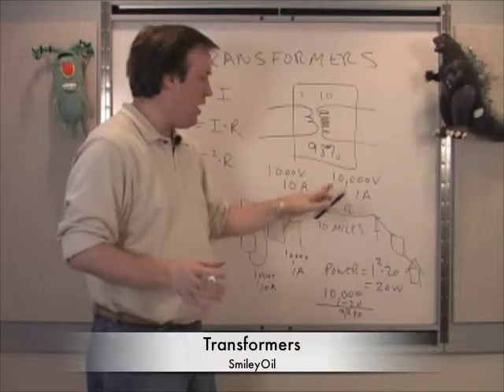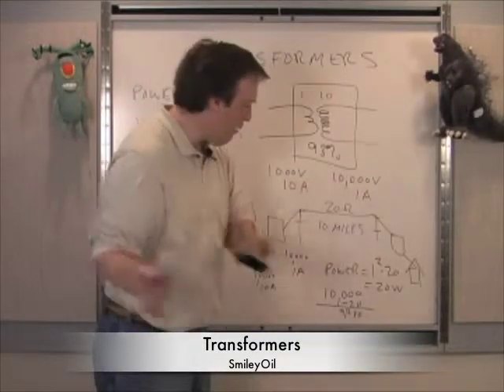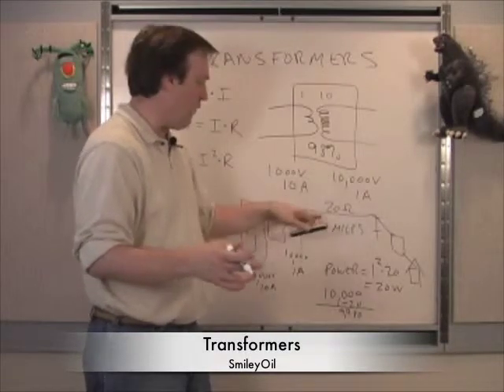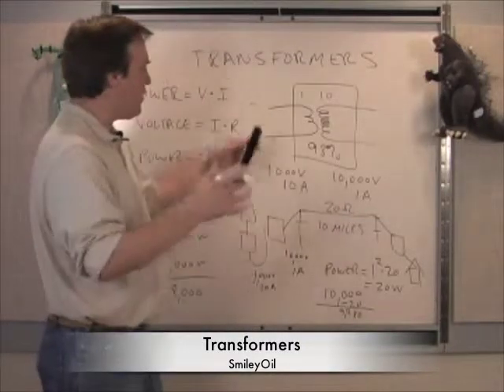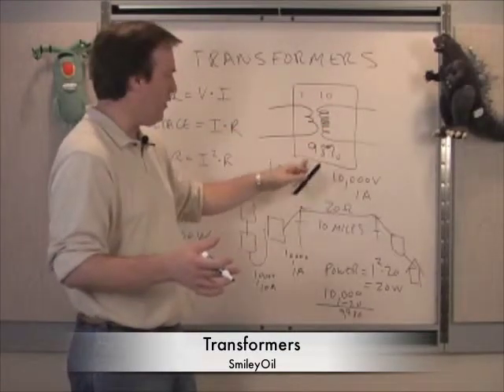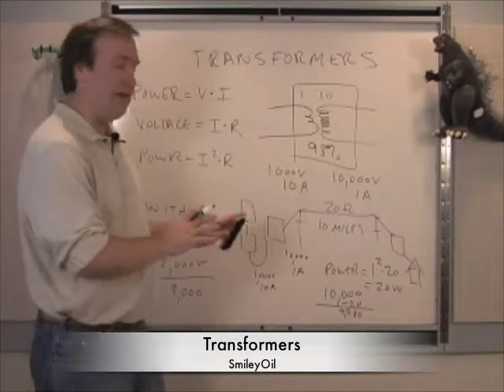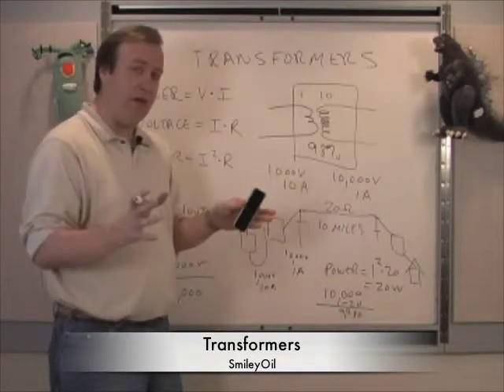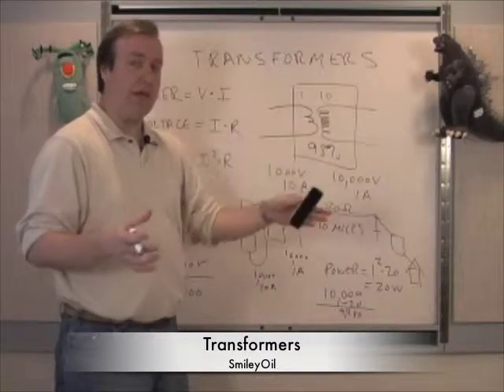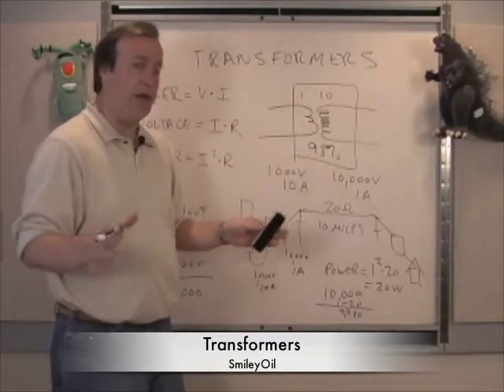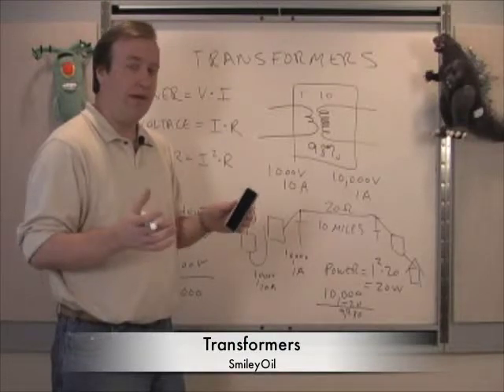When you want to send a lot of power, it's voltage times current — the higher the voltage, the lower the current needs to be. You're fighting resistance, so you use really heavy gauge wires to get ohms per mile way down. That transformer — that magical device that moves power from one side to the other with only 2 percent loss — can dramatically reduce losses from the power station to your house. Between your house and the real grid there are a minimum of five transformers, five different stages stepping voltage up and then stepping it back down. This is the backbone of the grid.